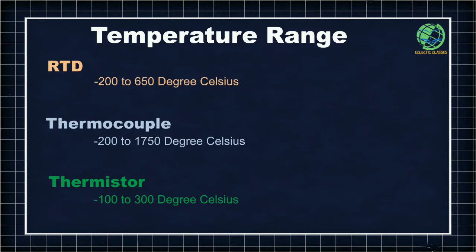In terms of temperature range, thermocouples have the widest temperature measurement range, from minus 200 to 1750 degrees Celsius. RTDs are capable of measuring temperature from minus 200 to 650 degrees Celsius. Thermistors can measure temperature from minus 100 to 300 degrees Celsius.